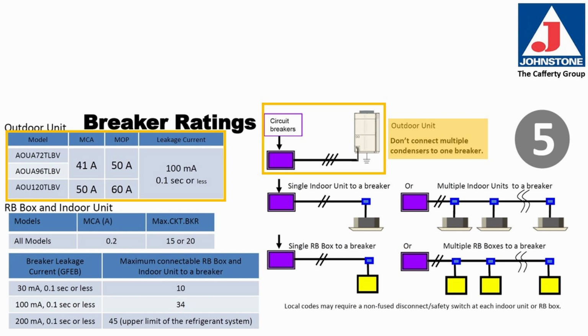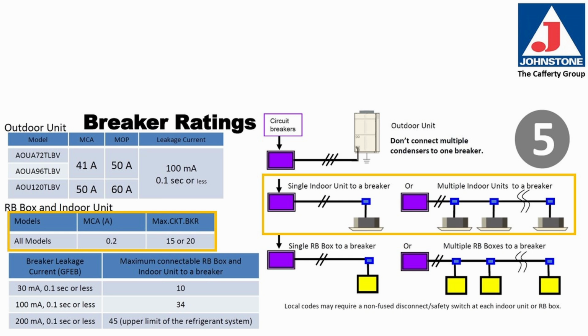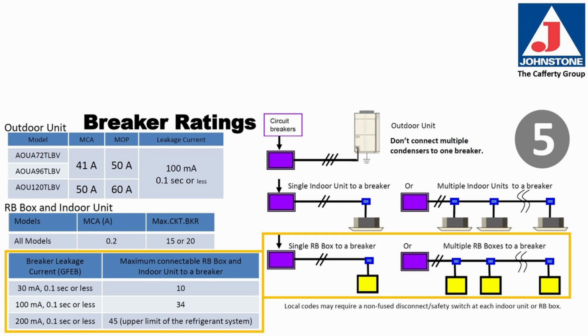For the outdoor unit, listed are the ratings for the 72, 96, and 120,000 BTU outdoor units. Each outdoor unit requires its own breaker. Do not connect multiple condensers to one breaker. The RB boxes and the indoor units are much lower amp draw, so you can wire a single indoor unit on a breaker, or you can wire multiple indoor units on one breaker. You can also wire a single RB box on a breaker, or multiple RB boxes on a breaker. See the chart to the left and in the installation manual for more information.